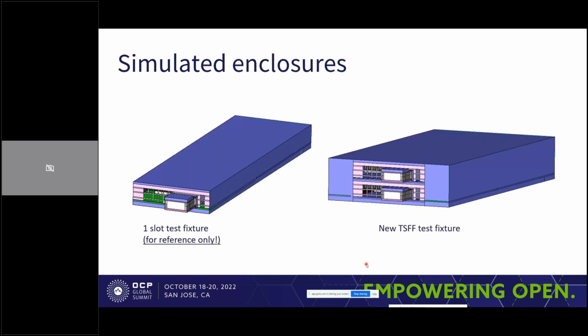This is two enclosures - this is the big one, it's the TSFF, this is the small one, it's the one-slot. You can see here these brackets, so you have only one card inside this fixture. I used in both cases the inlet airflow as a boundary condition, so I just put on this edge the fixed airflow - 300 LFM, 400 LFM, and so on for both cases. So the average cross-section velocity is the same for both fixtures.